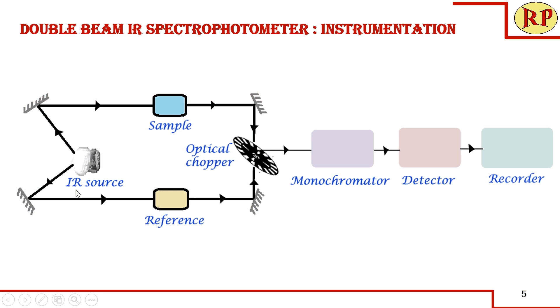We can also use a beam splitter where it splits the single beam into two equal beams — one passes through the sample and the other through the reference. We assume that the reference does not absorb any IR radiation; in case it does, the absorption will be nullified during comparison with the sample. Each covalent bond within the molecule absorbs IR radiation at a particular frequency, and after absorbing that light, the remaining light is transmitted.